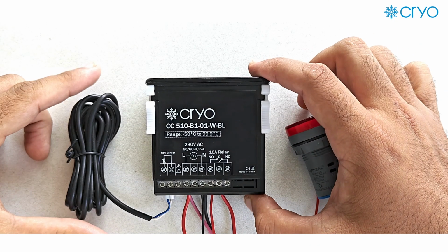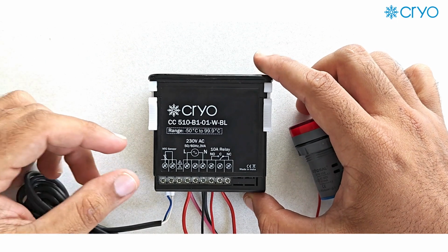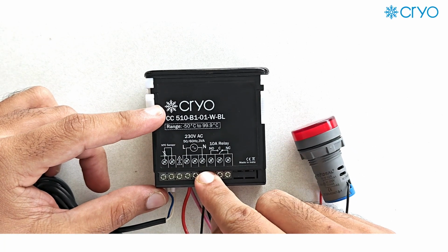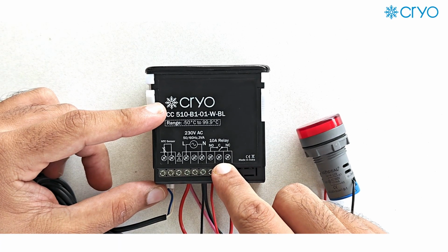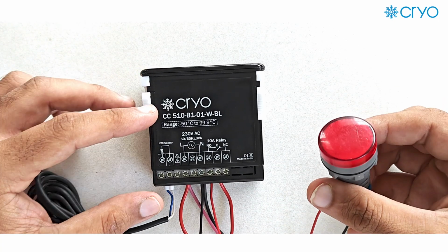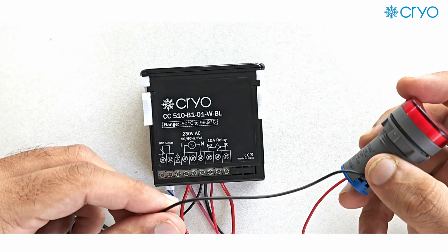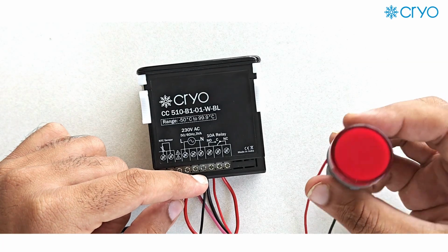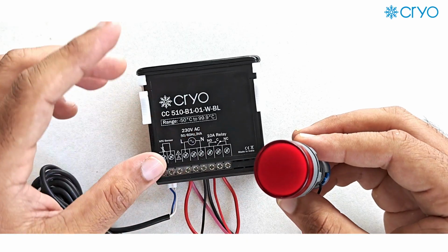Now moving on to the wiring connections. So NTC probe is already connected with the meter itself. Now what we have done is, in line we have given one phase, and in the neutral we have given one neutral wire. So from line we have looped it to common, that is our C, and from NO we have taken one LED. Okay, so whenever the relay gets on, our LED will get on, and the second terminal of LED we have given it directly to the neutral of the meter. So whenever the relay is on, our LED will be on. Whenever the relay is off, our LED will be off.